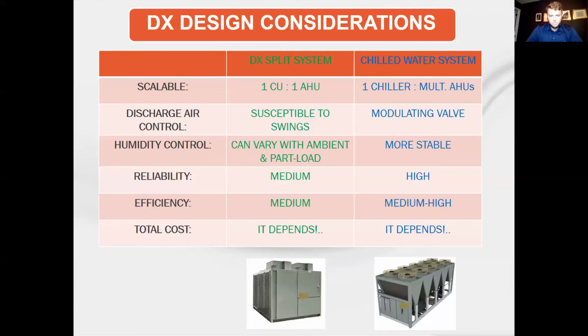Yeah, well, that total cost at the bottom, we did look at a project just recently that we'd sold that we repriced with chillers. The original system had two rooftop air handlers sitting right next to each other. One had a 100-ton condensing unit in it, the other one had a 60-ton condensing unit in it. So we repriced it with two air-cooled chillers and some pumps, and surprisingly it wasn't that drastic of a difference. The contractor said the piping might be about a wash, with all the complications of the refrigeration piping versus just a simple chilled water loop. So it wasn't an order of magnitude difference by any stretch of the imagination. So it's worth taking a look at.